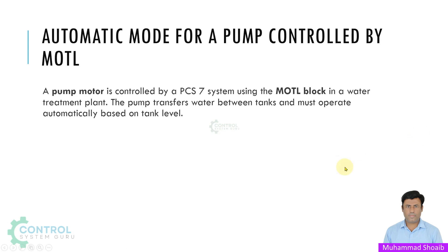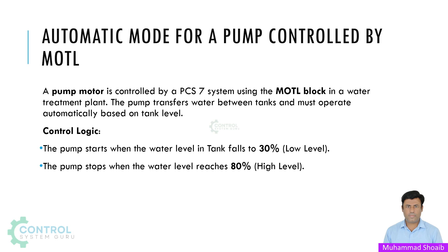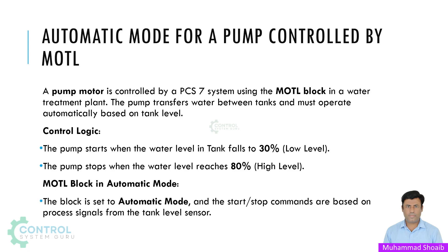In this tutorial video we have a water treatment plant where a tank is filling with water, and a motor is controlled based on different tank levels. For example, the motor will start when the water level falls to 30%, and once the water level reaches 80% the motor will stop. The MOTL block is set to automatic mode with start and stop commands based on the process signal from the tank level sensors.